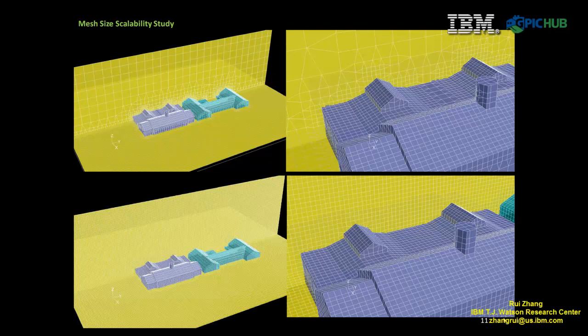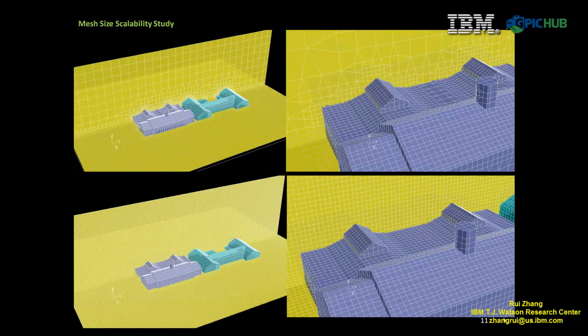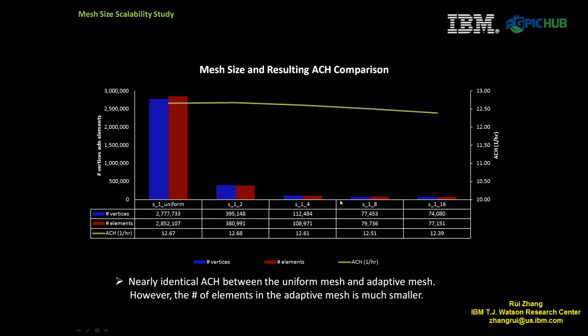The figures show the generated adaptive mesh and the uniform mesh. CFD simulations were conducted using both the uniform and adaptive meshes. The air change rates of Building 661 are summarized. As shown, there are no observable changes of air change rates between the results from uniform mesh and the results from the adaptive mesh.